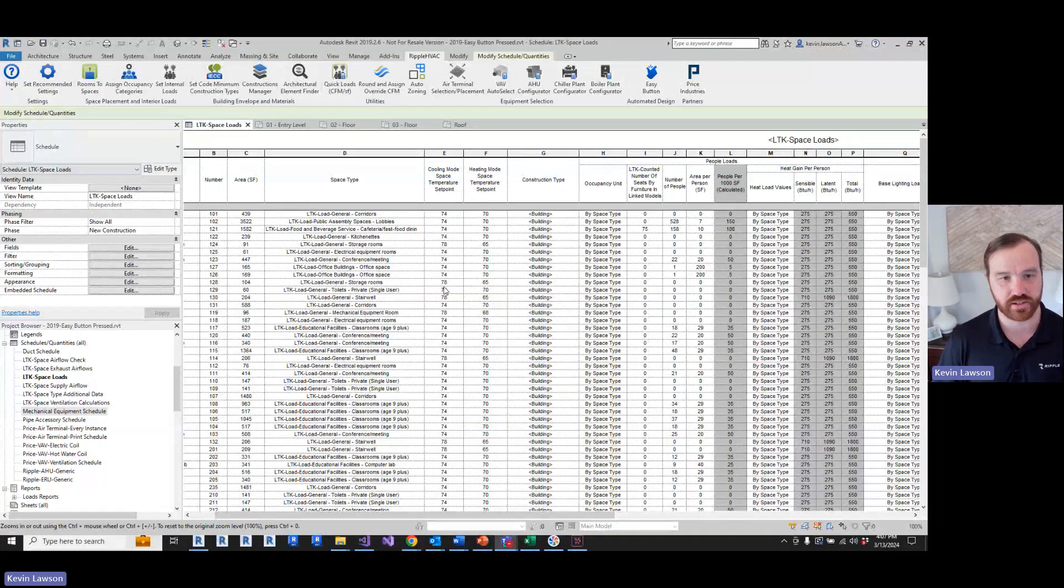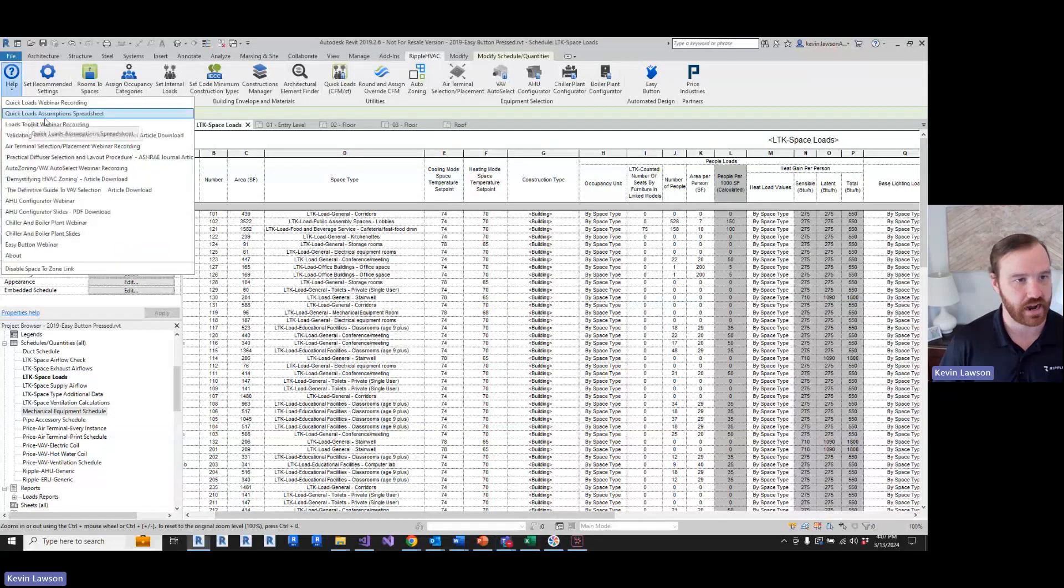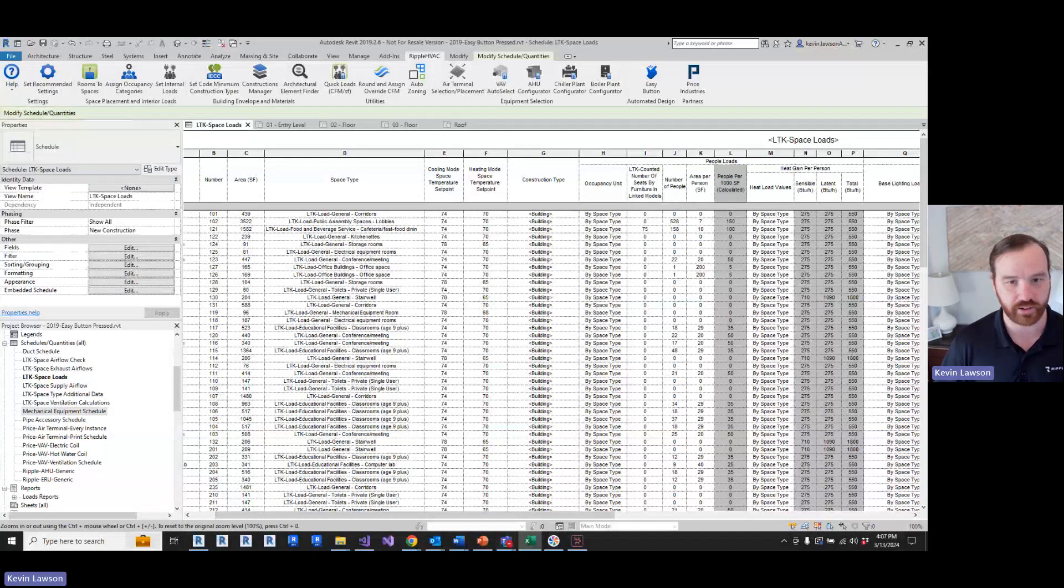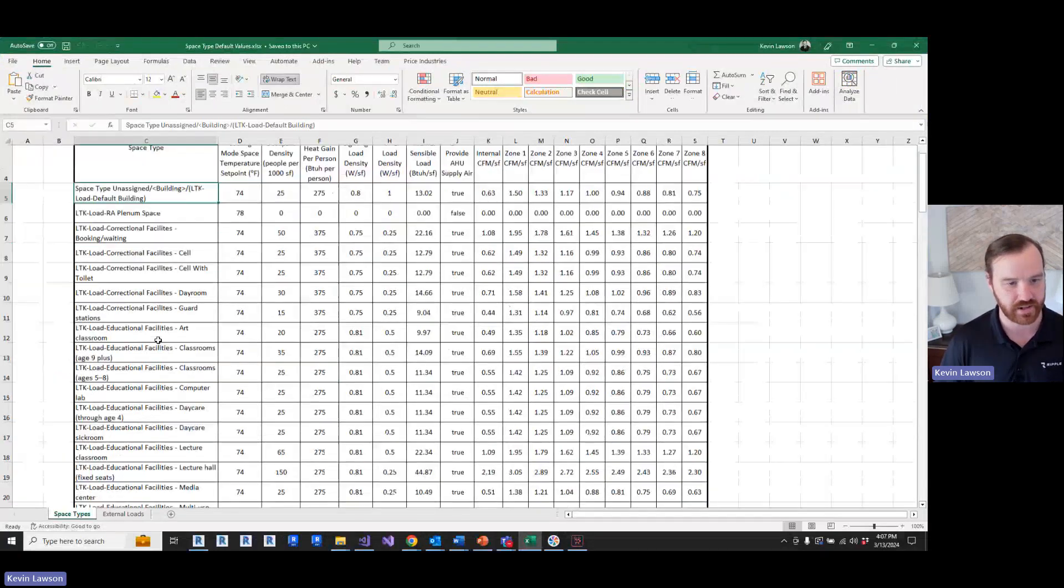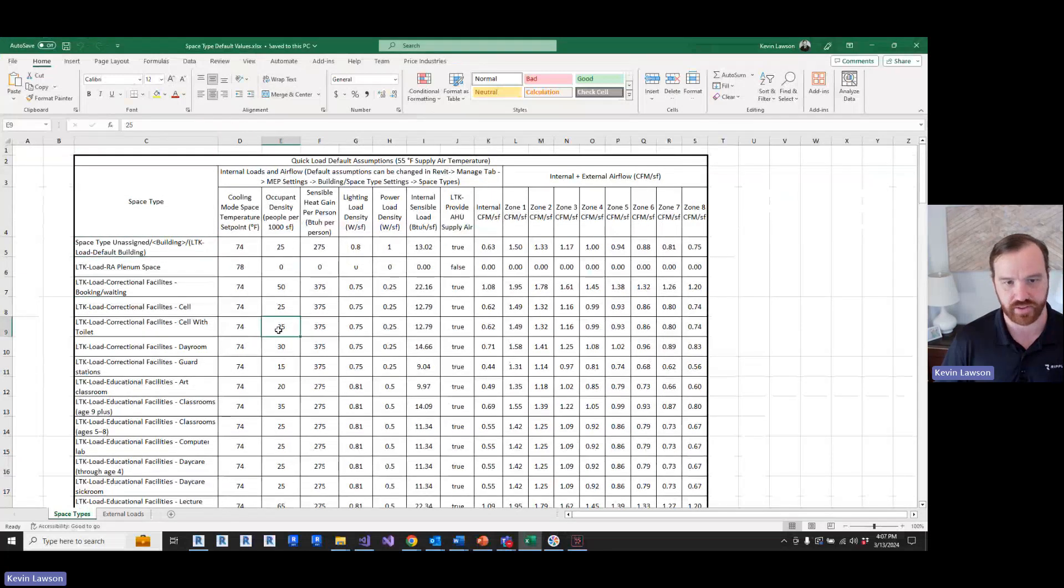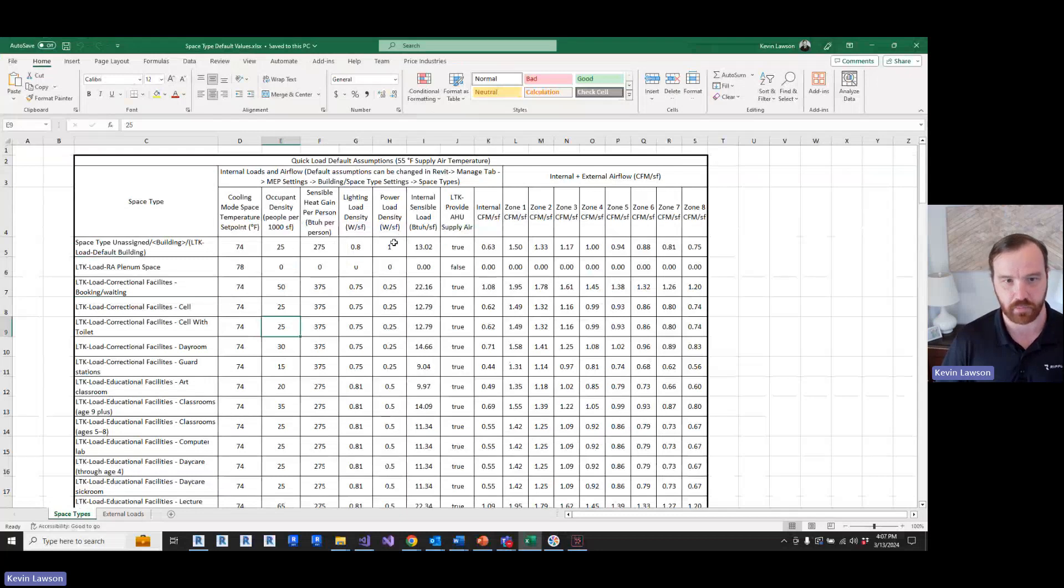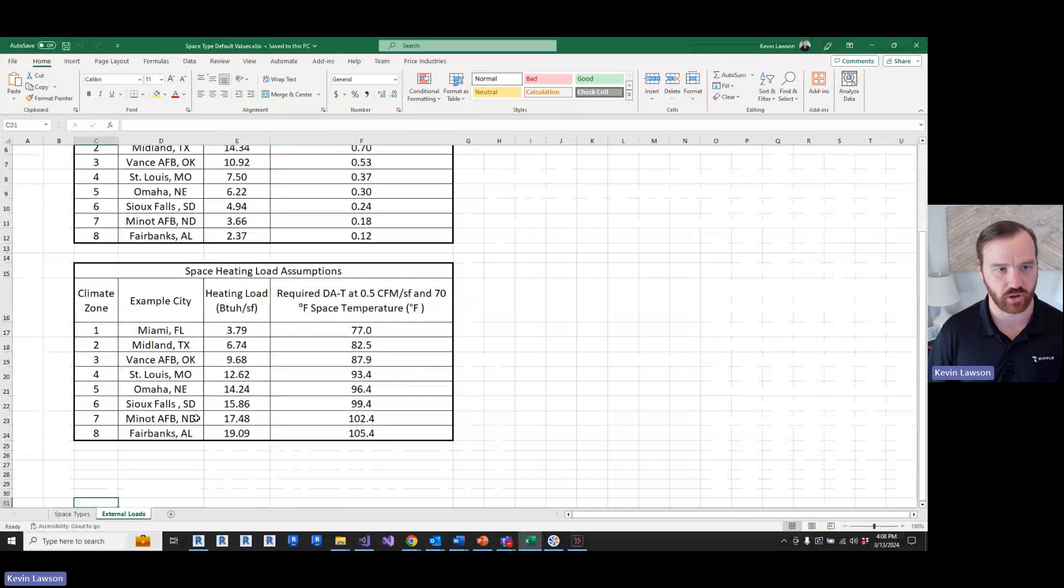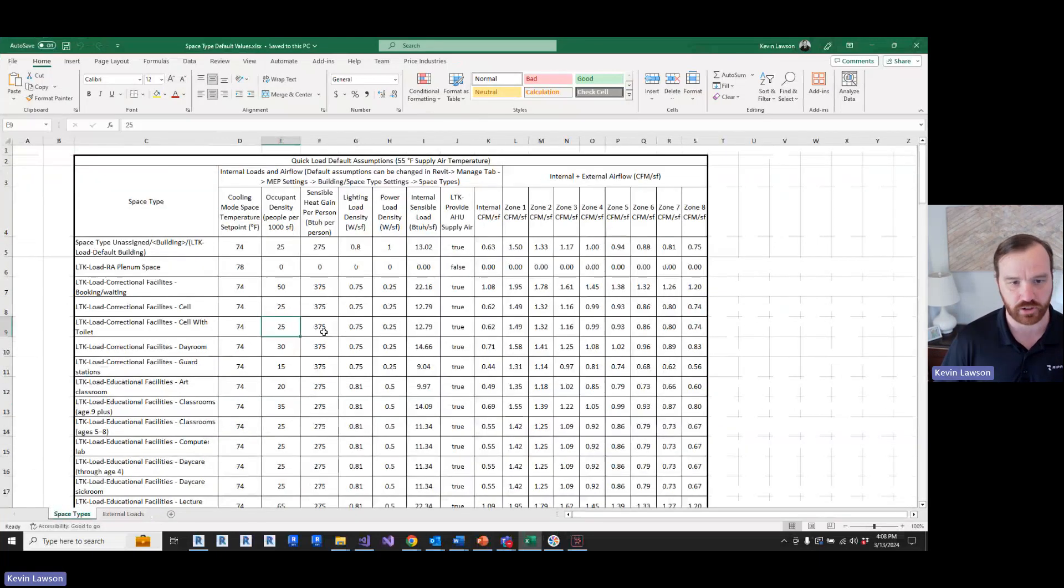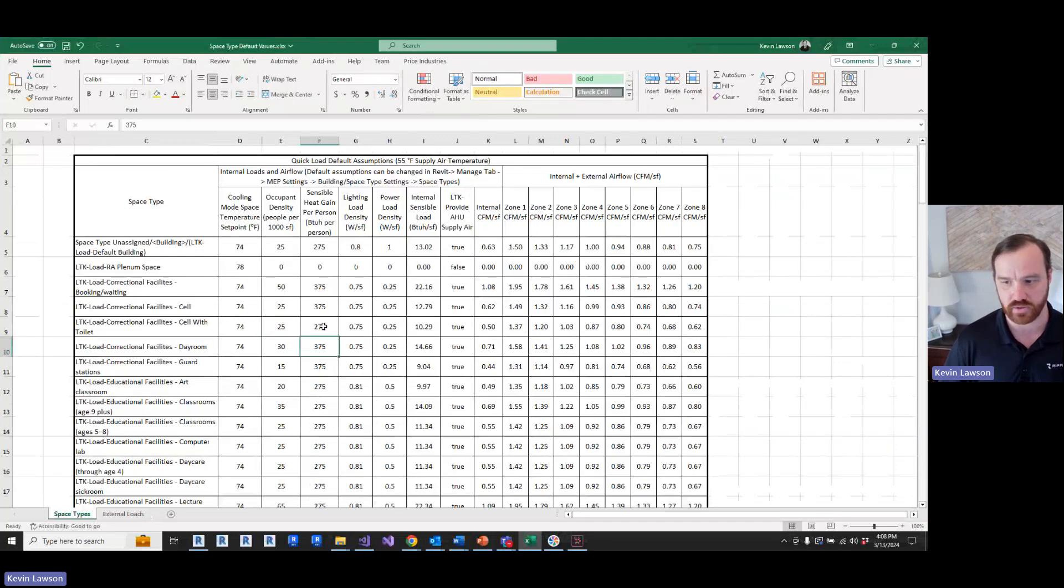So that is what's getting applied to all these spaces as far as the parameters go. If you would like to view the assumptions that Ripple is making altogether for all of the different space types, you could go here to help and download the Quick Loads Assumption Spreadsheet. That will download a spreadsheet where it will go through every single ASHRAE 62.1 space type that the Ripple Loads Toolkit builds, what the space temperature is, occupant density, sensible heat gain per person, lighting load, power load, total internal load, and then all the CFMs per square foot. And then the external loads are on the second tab. So you can view that at any time. And then if you want to change these, you can change these and it'll recalculate the CFM per square foot.